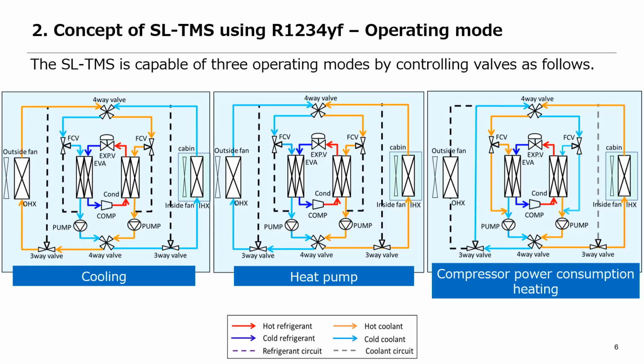Let us explain the operations of the SLTMS by focusing on the coolant flow, which can be controlled through valves to facilitate 3 distinct modes. The left diagram shows the cooling mode, the middle one is the heat pump mode, and the right one is the compressor power consumption mode. In all 3 modes, the coolant follows distinct flow circuits, while the refrigerant circuit remains consistent. The refrigerant circuit operates in a cyclical manner, starting with the compression of hot, high-pressure gas in the compressor, followed by condensing in the condenser. This is then expanded in the expansion valve, evaporated in the evaporator, and finally, the cold, low-pressure refrigerant gas returns to the compressor. Let's now delve into the specifics of coolant movement for each mode.